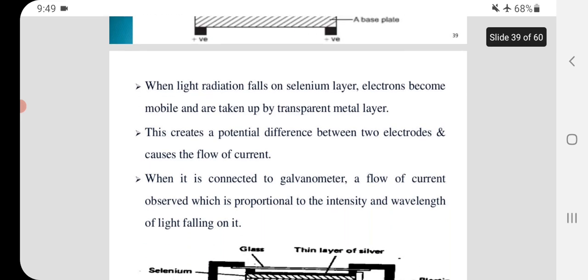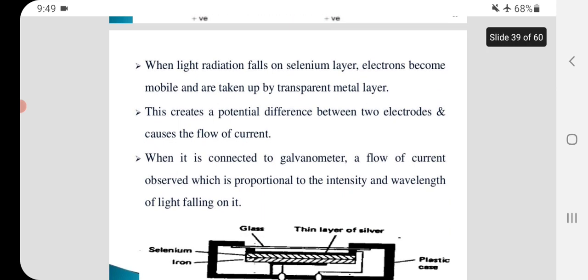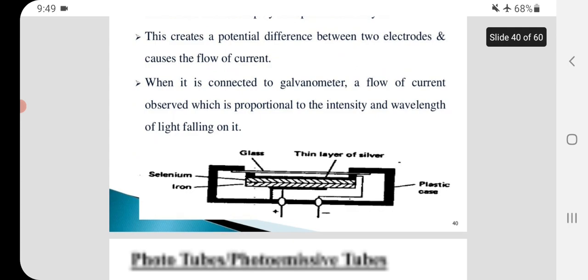When light radiation falls on selenium layer, electrons become mobile and are taken up by transparent metal layer. When it is connected to galvanometer, a flow of current is observed which is proportional to the intensity and wavelength of light falling on it.